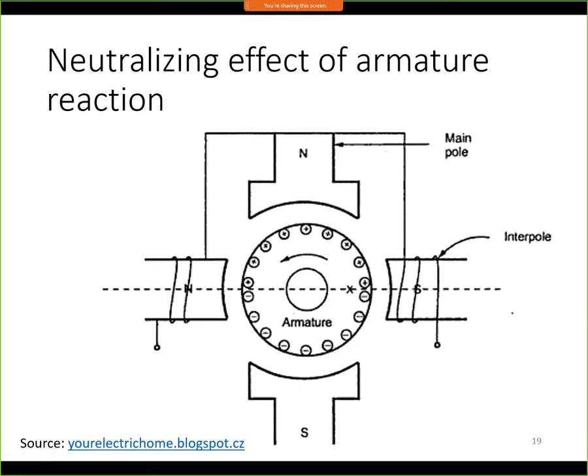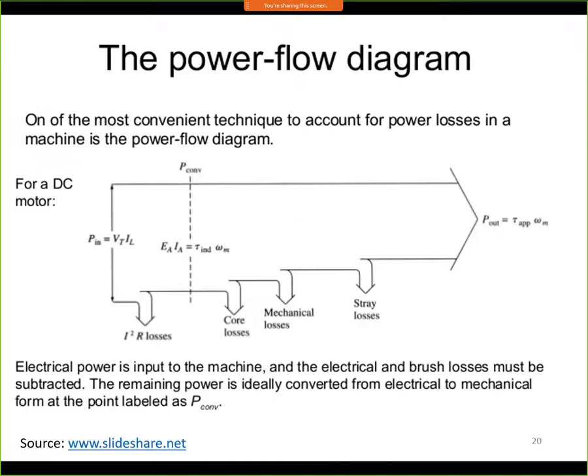To neutralize the effect of armature reaction, one way is to rotate the brushes. Another way is to create an auxiliary magnetic field using interpoles that suppresses the interaction. The interpole is a smaller pole placed at 90 degrees relative to the main magnetic pole.